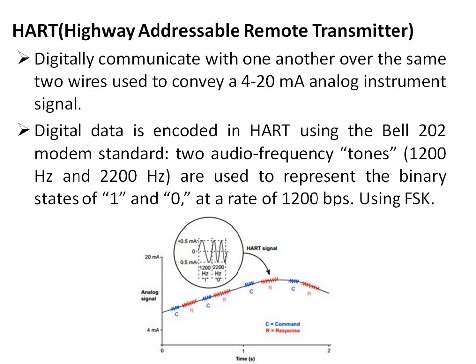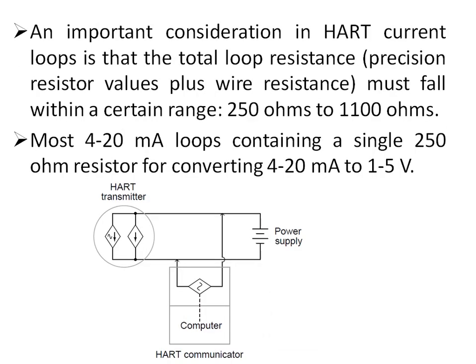The HART signal is an AC signal with a peak-to-peak current of 1 milliampere. Since it is an AC signal, its average value is zero, so this AC superimposed on the same 4 to 20 milliampere loop does not affect the 4 to 20 milliampere DC signal.